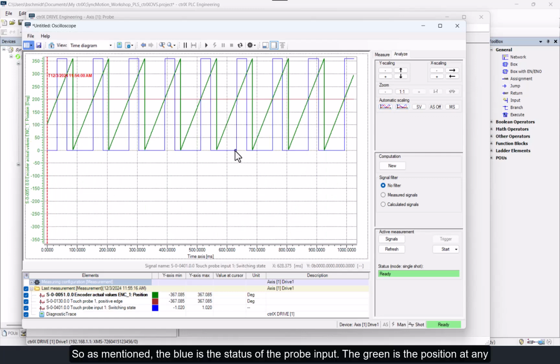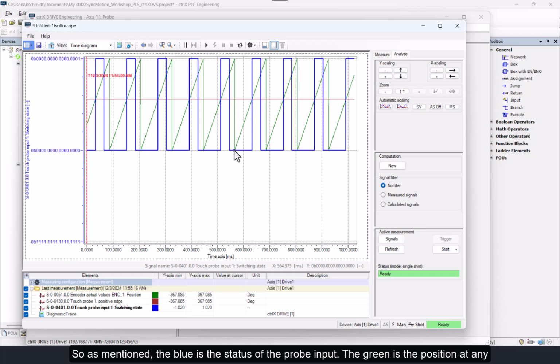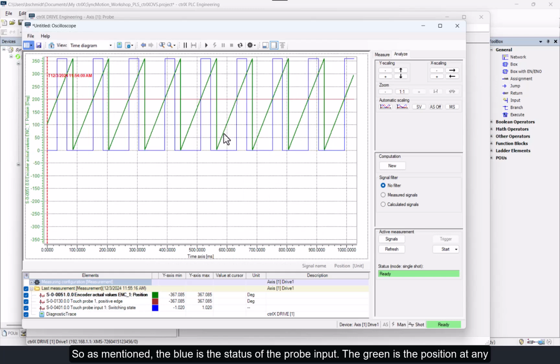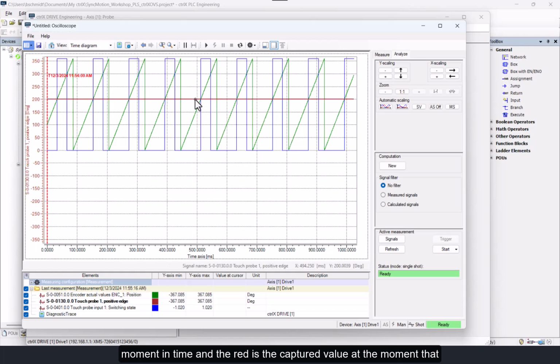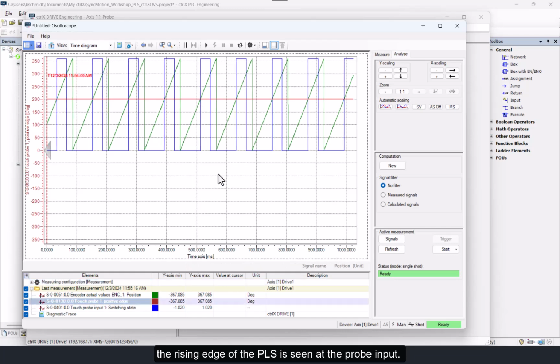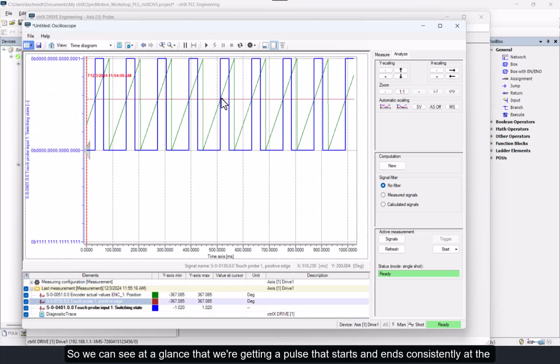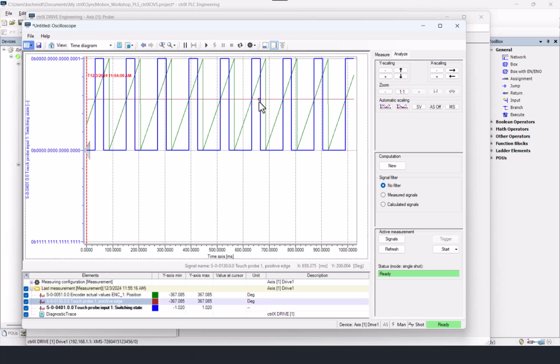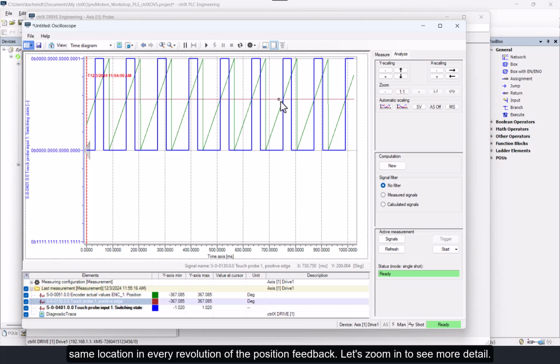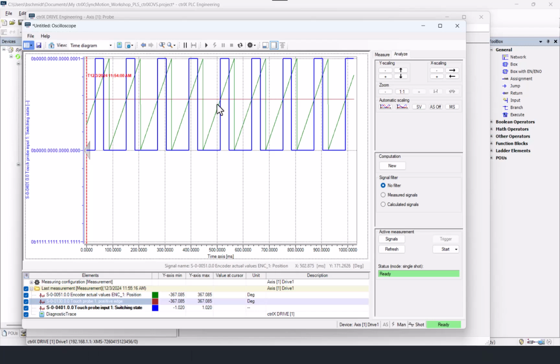So as mentioned, the blue is the status of the probe input, the green is the position at any moment in time, and the red is the captured value at the moment that the rising edge of the PLS is seen at the probe input. So we can see at a glance that we're getting a pulse that starts and ends consistently at the same location in every revolution of the position feedback. Let's zoom in to see more detail.